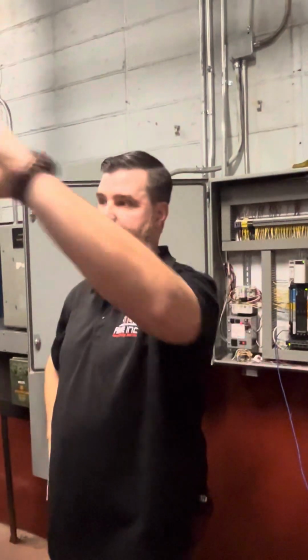I'm on the same page with Gordon that that should be 1/3, 2/3, 3/3. But if you're ever turning this one on, we should be manually switching all those off or shutting down that particular system. Well, according to the BMS, if this goes on, none of those are supposed to go on at all, and the reason is because the flue cannot handle it.